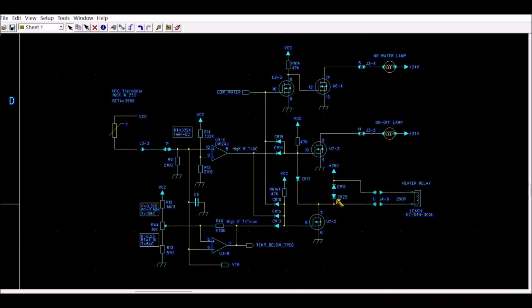The third output is the heater relay. It is activated when the temperature here is below the temperature set by this trimmer. The relay is also off when the temperature is below 0 degrees, and it is deactivated when the water in the tank is not high enough.